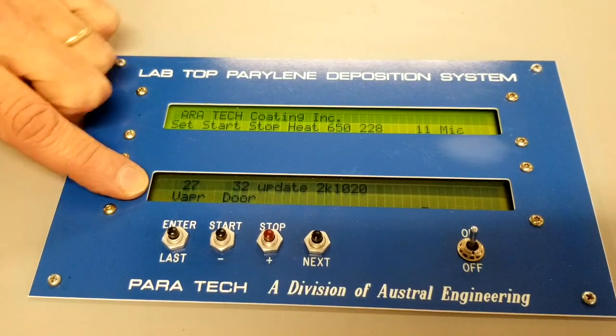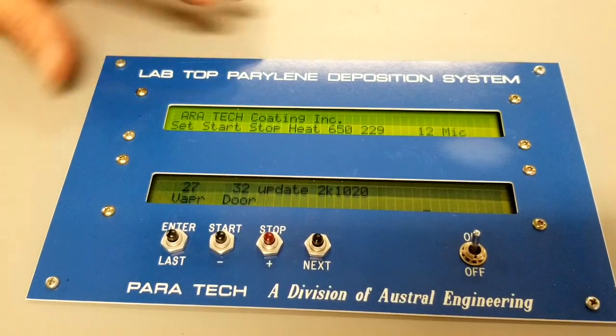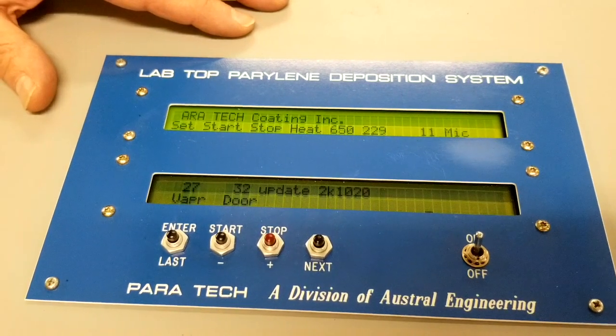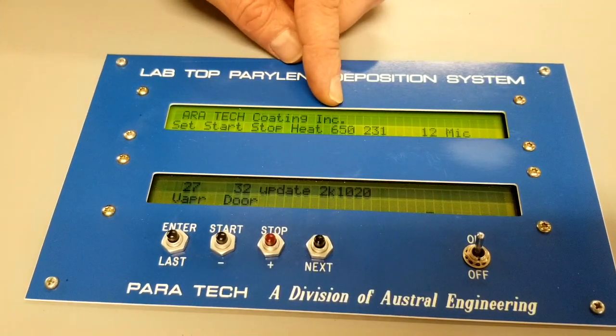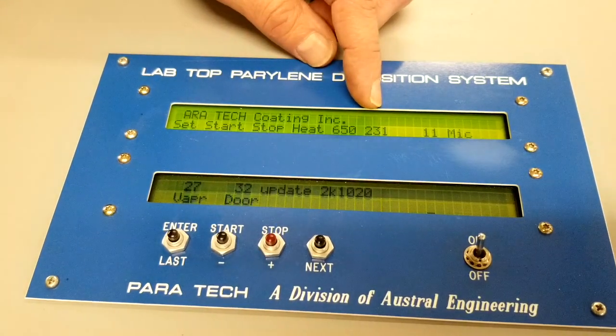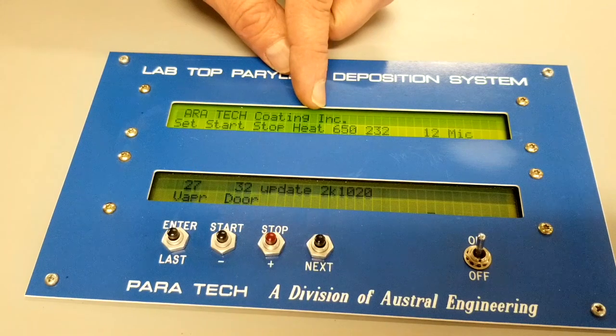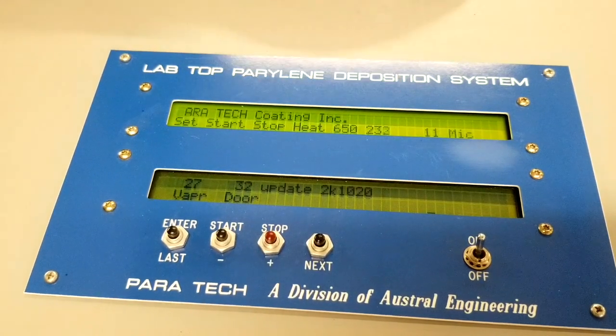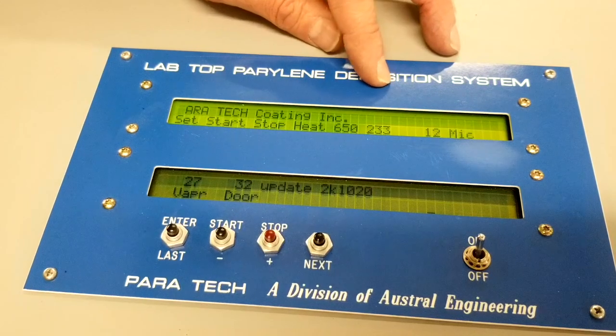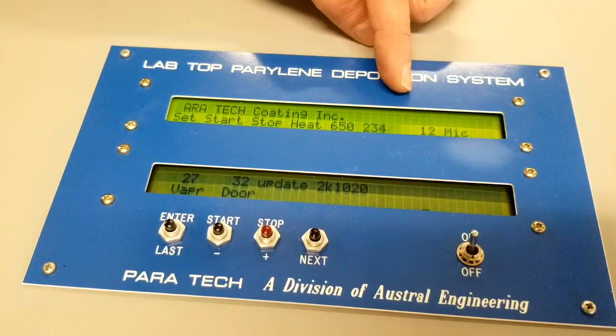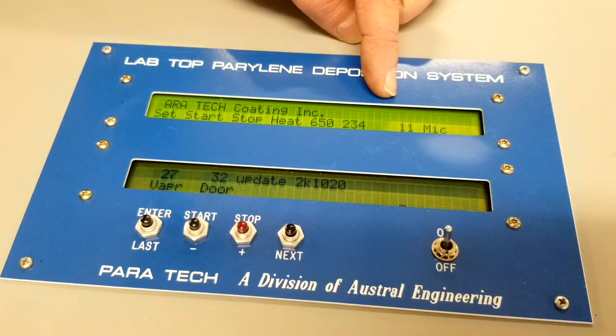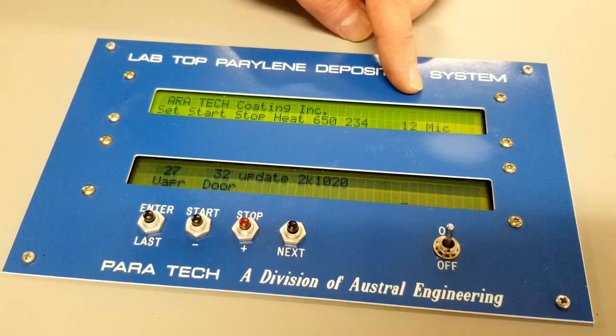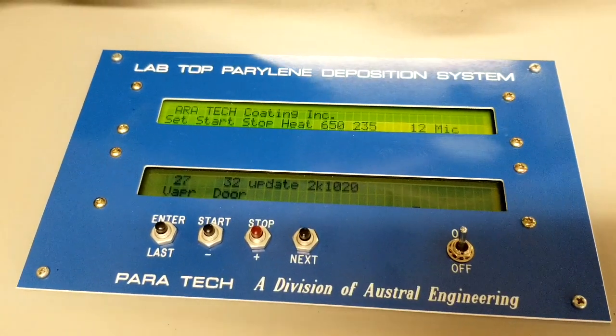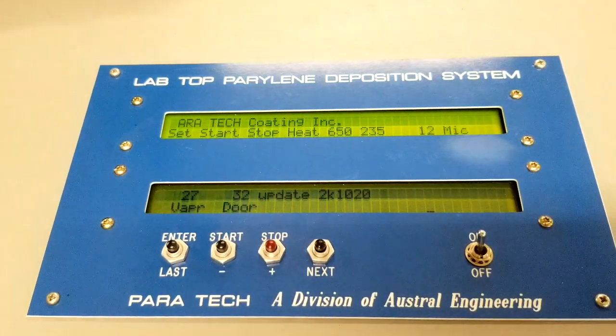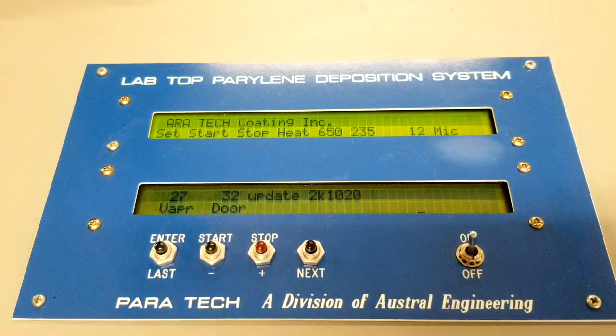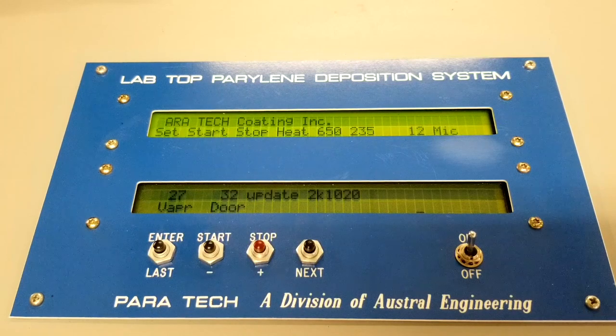So we're seeing our vaporizers at 27C. The door's at 32 right now. It's in idle mode. And the 650 is your pyrolysis tube, and this is your post heater. So you're at 650 in a tube, and right now you're at 233 for the post heater. And this is your vacuum indication right here. We're at 11 microns. And we have our cold probe located inside its port right there, and it's running at minus 80 degrees Celsius.